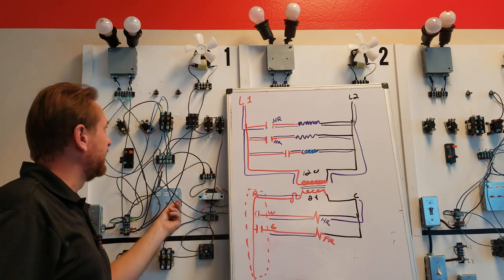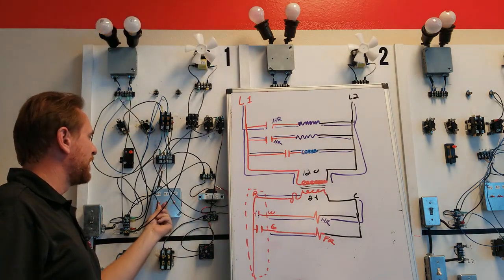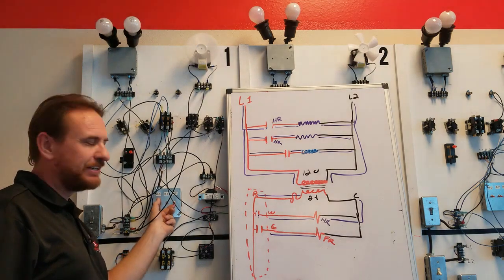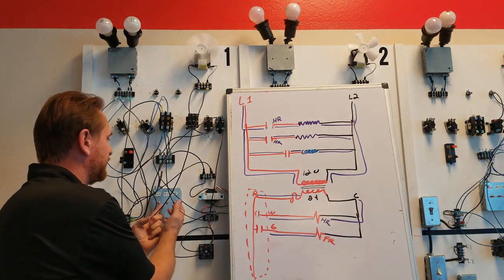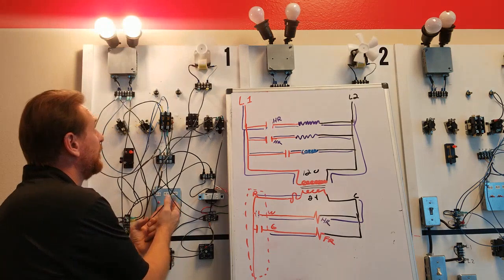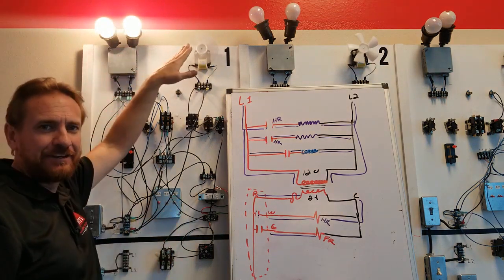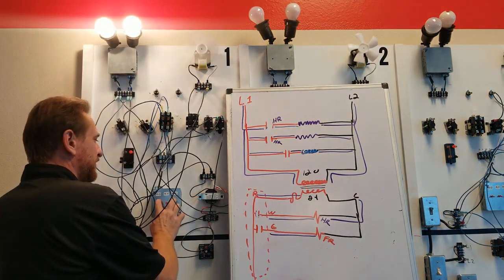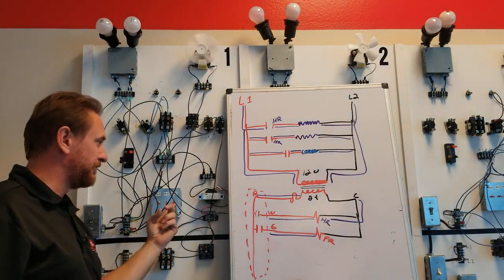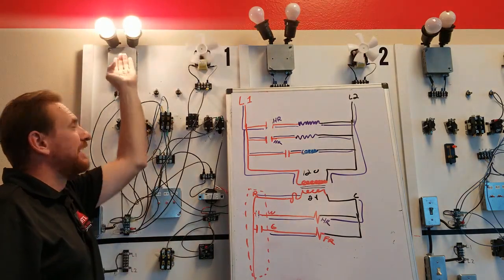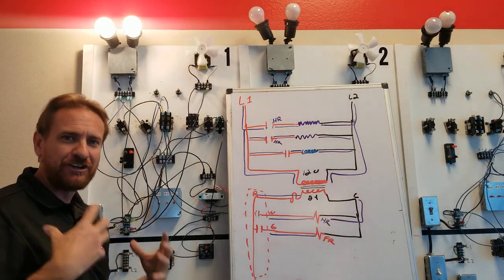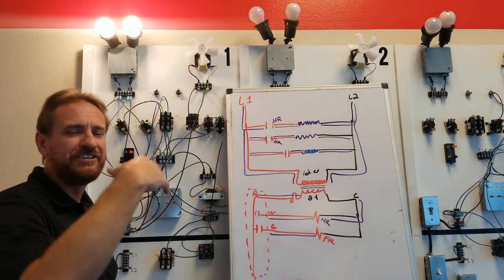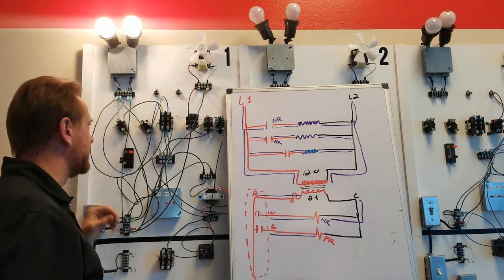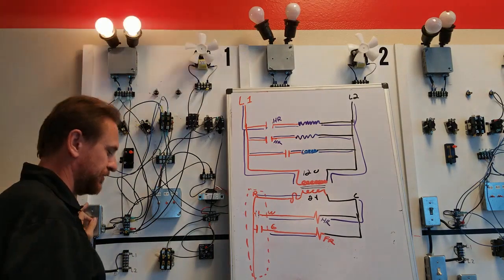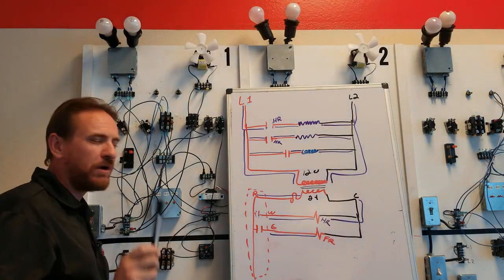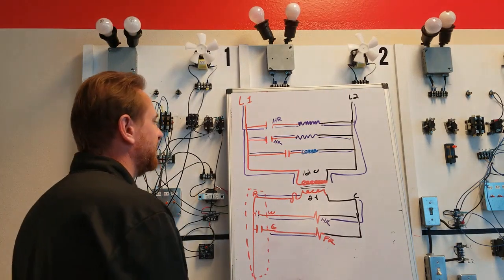So now when I call for heat, my heater comes on. When I call for fan, my fan comes on. And if the thermostat calls for fan and heating at the same time, we'll be running our heat elements and our fan motor. The problem is there is still the possibility that when we call for heat, my heater is on, but the fan's not. So we're having all that heat built up in this furnace. It's not going into the house. We're going to overheat on a limit or cause a fire issue. So what we're going to do is add one wire to simplify all of this.